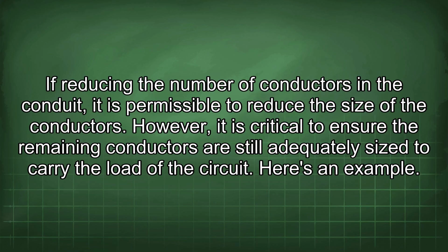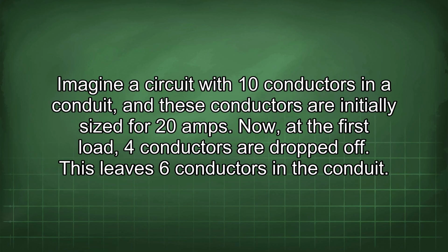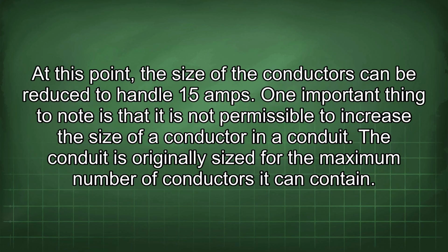Here's an example. Imagine a circuit with 10 conductors in a conduit, and these conductors are initially sized for 20 amps. Now, at the first load, 4 conductors are dropped off. This leaves 6 conductors in the conduit. At this point, the size of the conductors can be reduced to handle 15 amps.